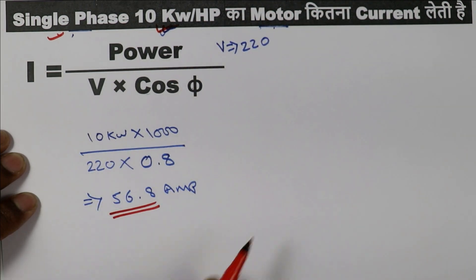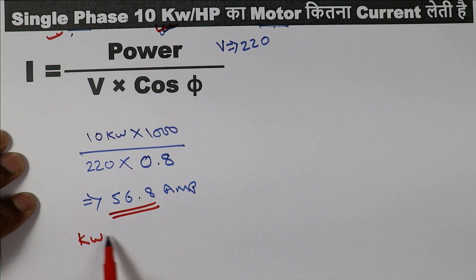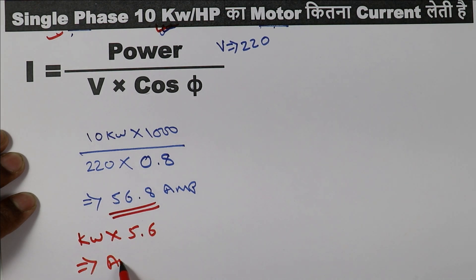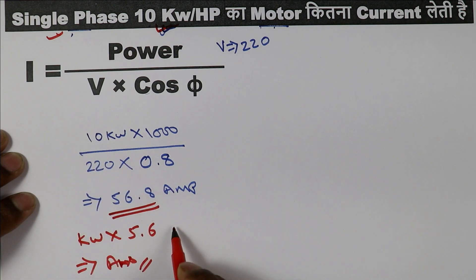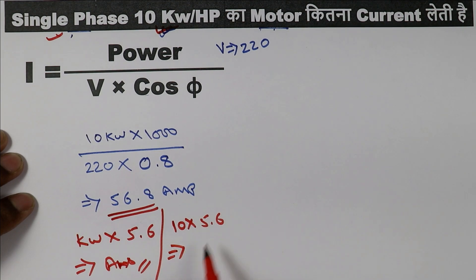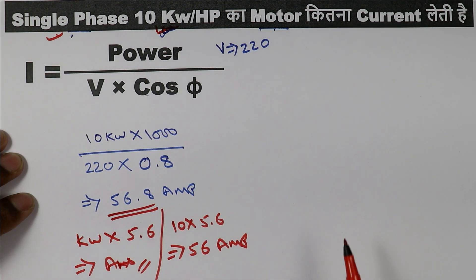For the short trick for a single-phase motor with kilowatt rating: simply multiply kilowatt by 5.6. For a 10 kilowatt motor, 10 multiplied by 5.6 gives 56 ampere. You can see the exact answer was 56.8 ampere and we got 56 — almost the same answer.